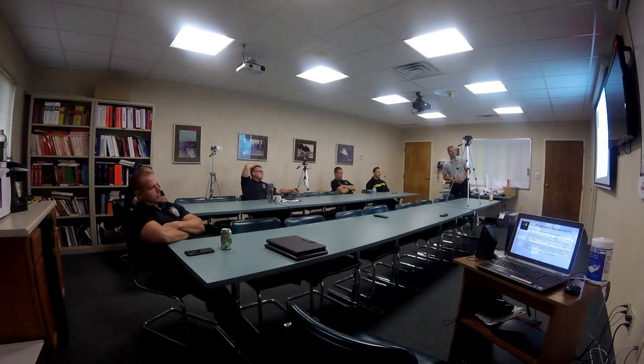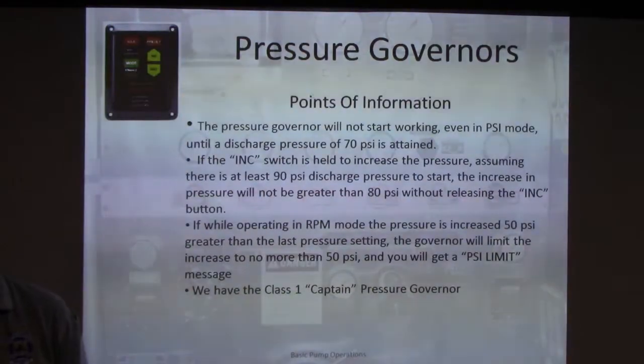So is that 80 psi in addition to your net pump pressure? Yes, your static pressure, anytime you push it, wherever it's at. It could potentially be like 180 if you're not paying attention. Well, if you have it set to 150, it could go up another 80.